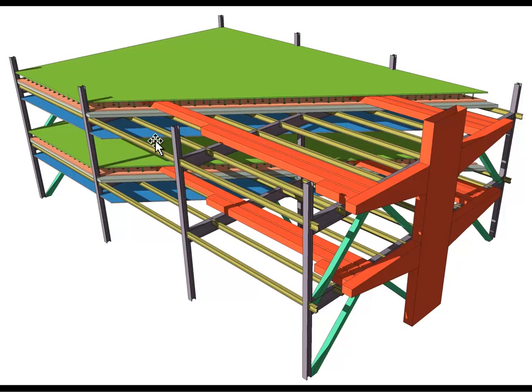A second reason for continuous plenum volume in both floor and ceiling is building flexibility. The client wanted the ability to rearrange interior partitions at any time and still get air to any new space. A plenum volume provides that power: any occupied floor area has supply plenum below and return plenum above, eliminating the need to rearrange ductwork under the floor or above the ceiling whenever the layout changes.